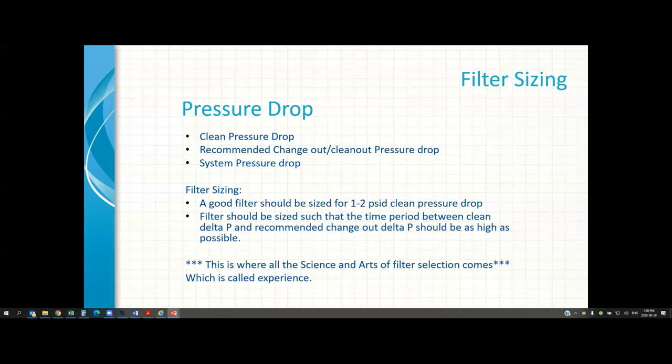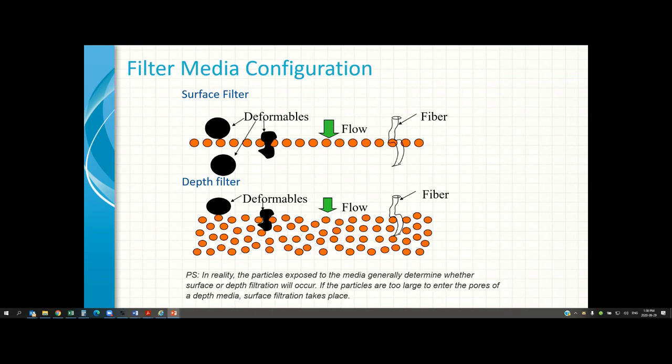Filter media can be divided into two main categories: surface filters and depth filters. Surface filters are like your patio screen — not letting bugs in. Under pressure, surface filters may let some fibers or deformable particles through. Depth media, like thick cartridge filters or sand filters, are good at holding organics, deformable solids, and fibers. Another type is adsorptive or charged filter media, where the media has a positive charge and negatively charged contaminants are captured by adsorption.